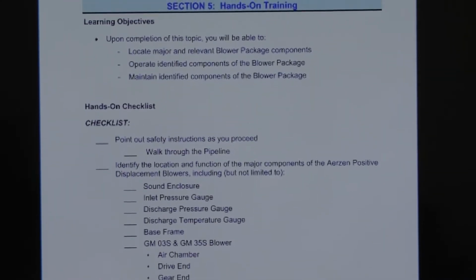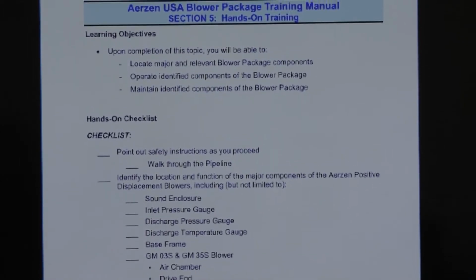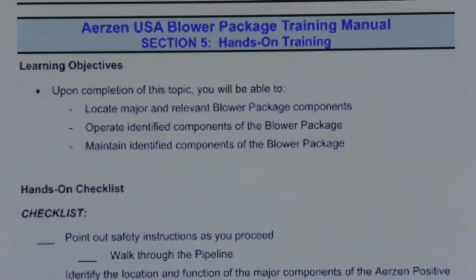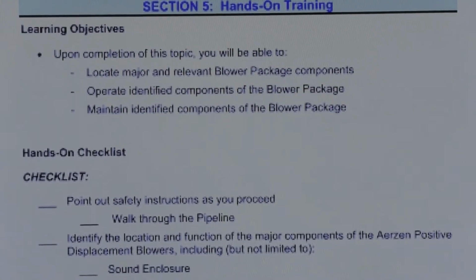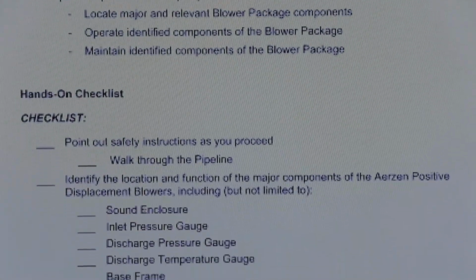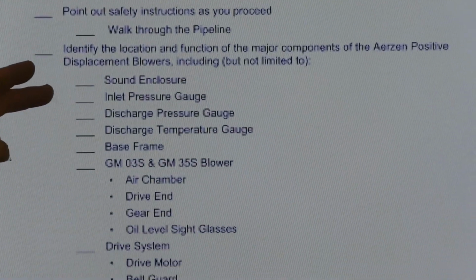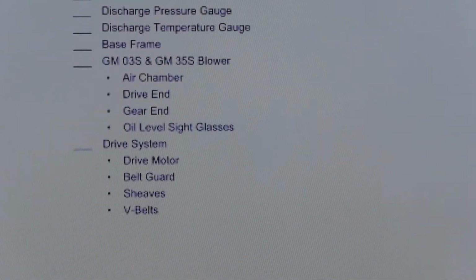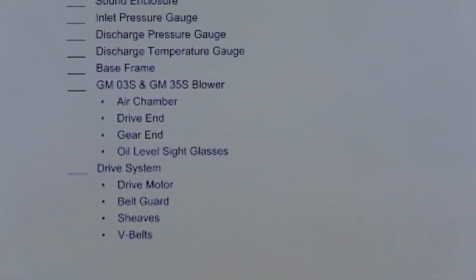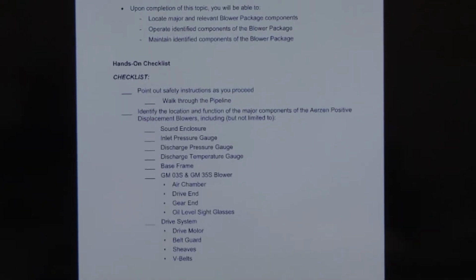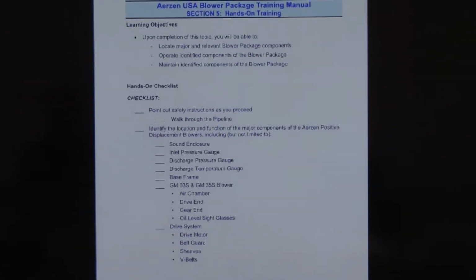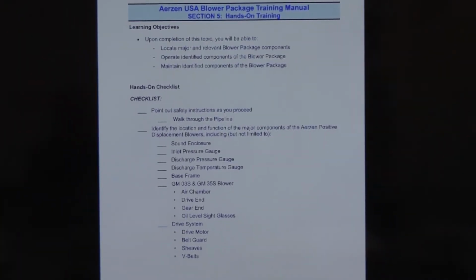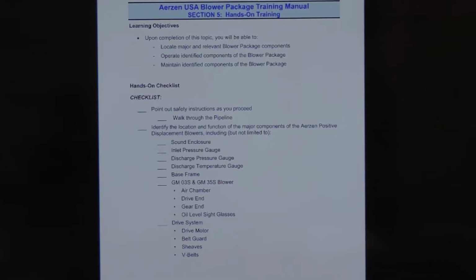All right, this is what we're going to look at when we go outside. The sound enclosures. These have the electronic controls, so I'll show you where you find the inlet pressure and discharge temperature. We're going to look at all the components inside the unit and how we go about changing the filters, the belts, and the oil, because those are your three primary maintenance items. And I'll show you where the other items are located physically on the blower. Next.